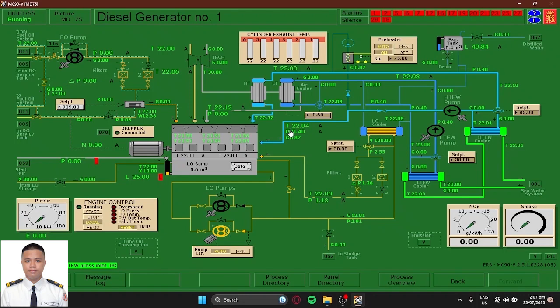So in the diesel generator, you have 4 systems to satisfy here. So you have the fuel, you have the starting air, the lubrication, and the cooling system. So we're gonna satisfy all of that first before we can start our diesel generator 1. So we're going to start here with our lubrication oil. In the lubrication oil, you just have to open this valve, fill this lube tank to 50 to 70. Let's just wait. There we go, we have achieved 50.